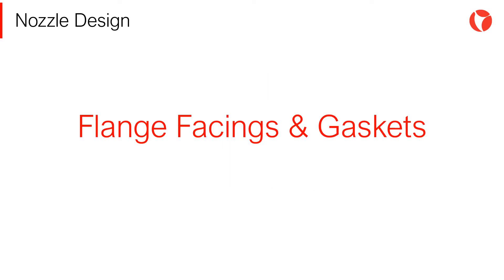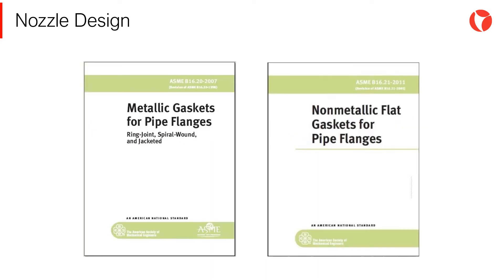Flange joints must warranty different tightness levels. Depending on the pressure vessel service — high pressure, low pressure, lethal, hydrogen, etc. — different types of flange faces are used as the contact surfaces to seat the sealing gasket material. The different types of gaskets to be used for the design of pressure vessels are indicated in the code. They can be metallic or non-metallic, and can be made out of rubber-coated steel, solid steel, resins, and spiral-wound steel.